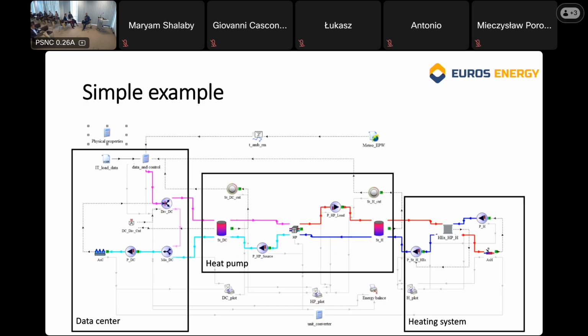We have a heat exchanger where the heat for the internal heating system of the building is warmed up. Heat from the data center is delivered to a storage tank. The heat pump moves this heat to another storage with a higher temperature. From this storage, heat is delivered to the heat exchanger and given to the internal heating system of the building. Up until the heat exchanger we have glycol liquid inside the pipes, in the cooling system and the heat pump, and after that we have a water system.